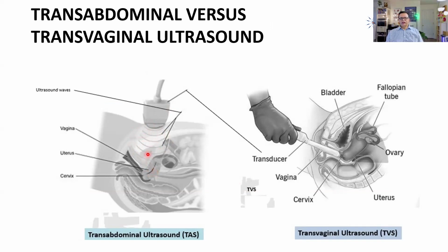So it's quite a distance, and because the ultrasound has to travel such a long distance, we cannot use a high frequency transducer. We have to use a low frequency, like 3.5 megahertz typically, and that allows the ultrasound beam to travel deep and to be able to image the pelvic organs.